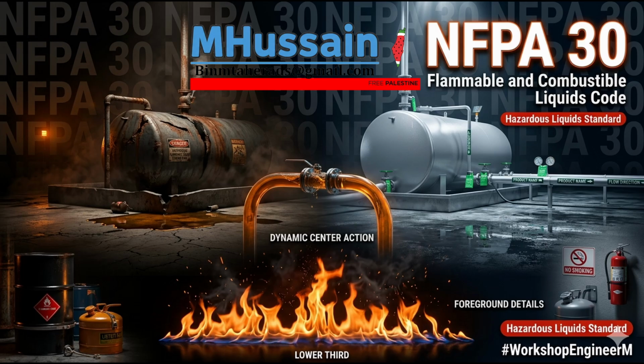This is Chapter 16, which covers automatic fire protection for inside liquid storage areas. It is easily the most mathematically dense section of the code. It really is. And the foundational decision an engineer makes here is picking the right suppression medium, namely automatic water sprinklers versus low-expansion foam water systems.